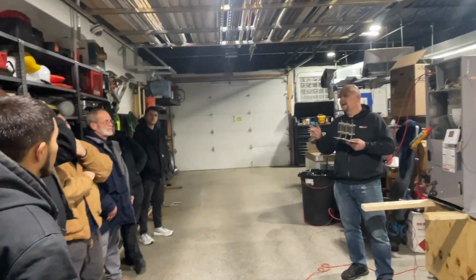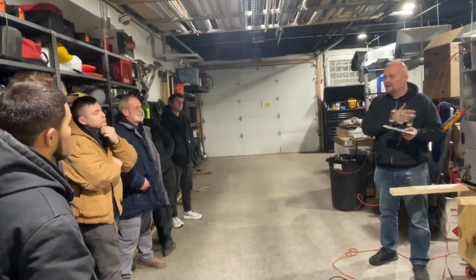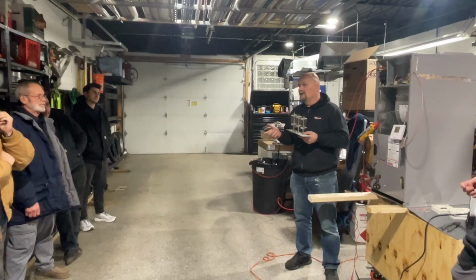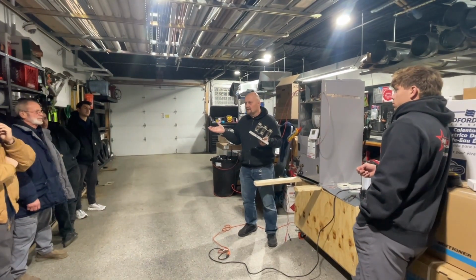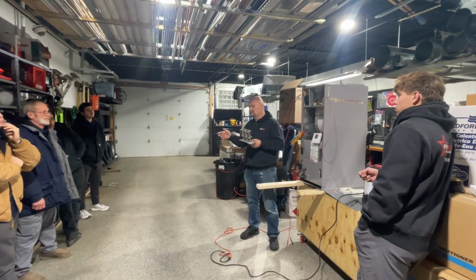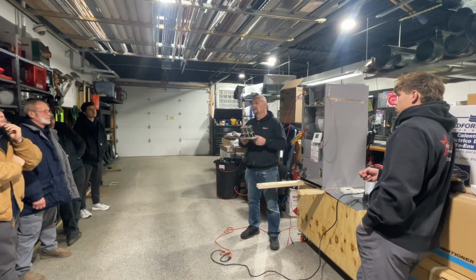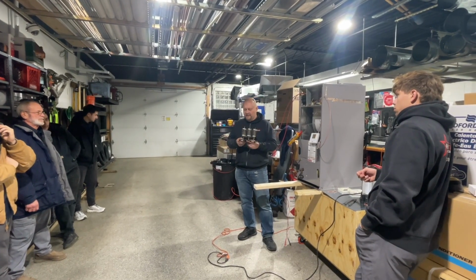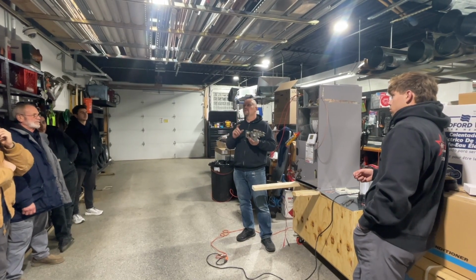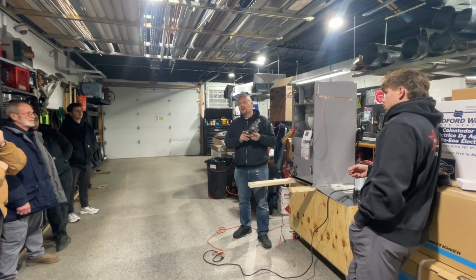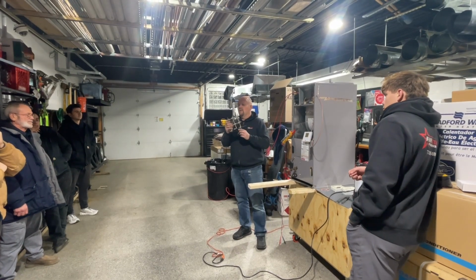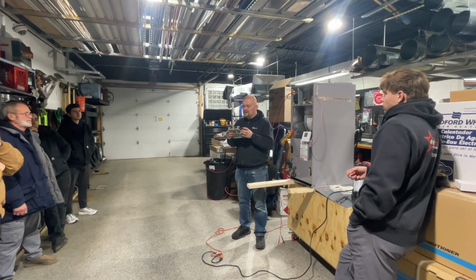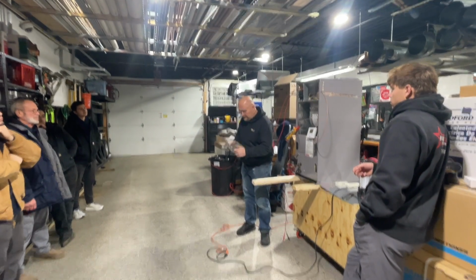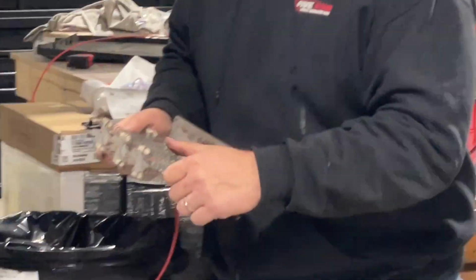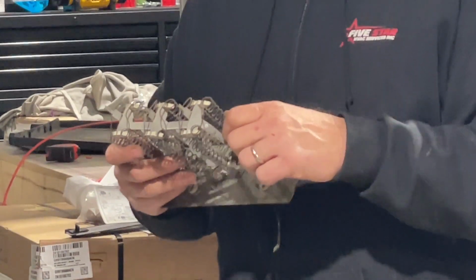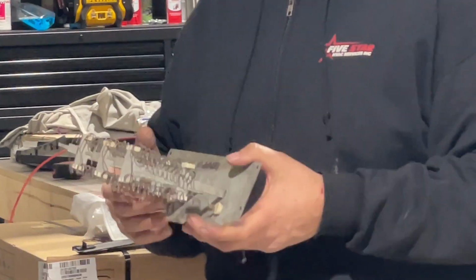So if you have a clogged filter, or if the fan isn't obviously functioning, or if it's set for too low of a speed, or if everyone's covered all the ductwork, right? Someone shut off all the supplies, the returns are covered with carpets. Same thing will happen, not enough airflow. And it may not be such a low amount of airflow that it'll trip the thermal switch, but it'll start affecting the way this cable is heating. So if this starts to overheat, it starts to get crusty. See, my hands are full of dirt. That's not just from working earlier, but you touch this, it starts to get brittle. Once it becomes brittle, it'll eventually snap and needs to be replaced.